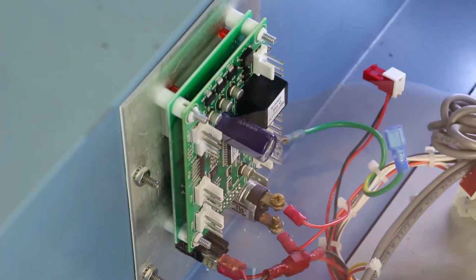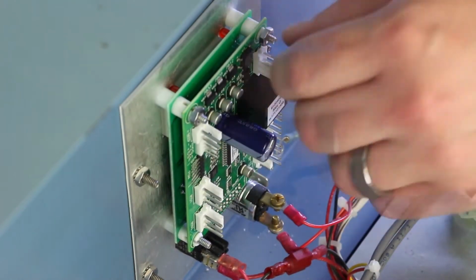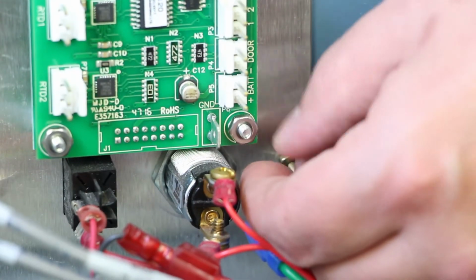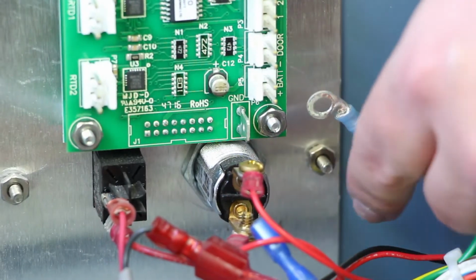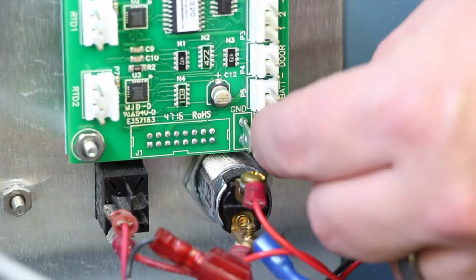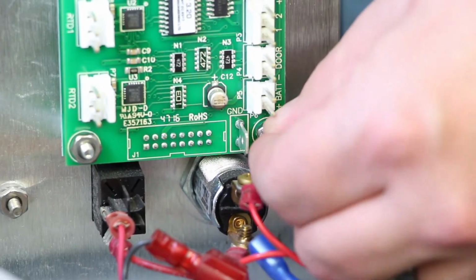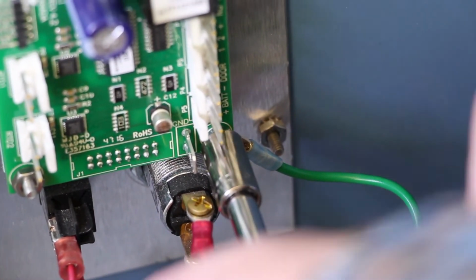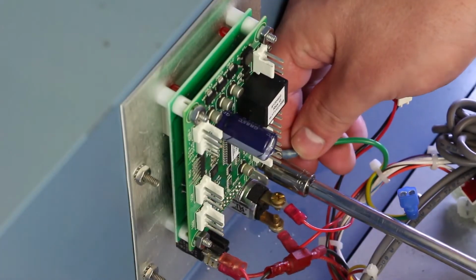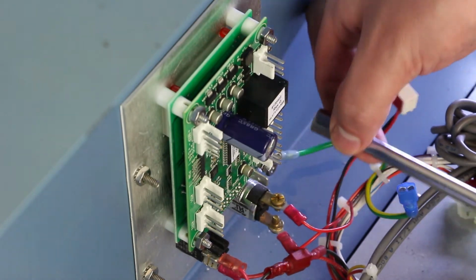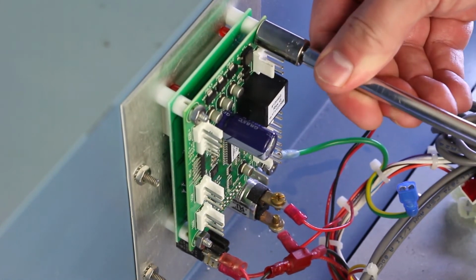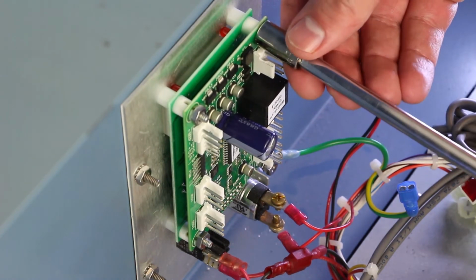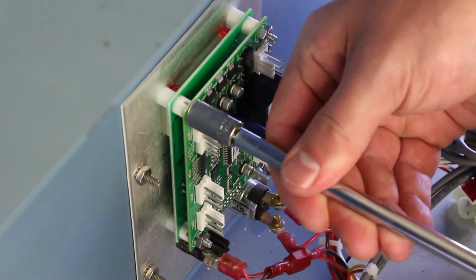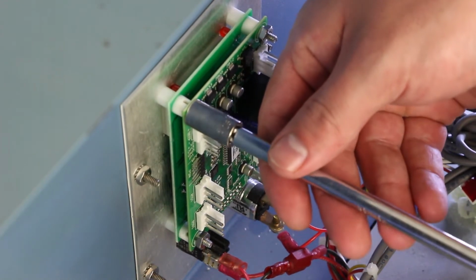Ensure the plastic spacers are in place between the circuit board and the back of the membrane. Use the 5/16 socket to tighten the nuts back in place. Take care not to over-tighten them, which can push the circuit board too far into the back of the membrane, activating the buttons even when they are not being pressed. If they're not tightened enough, the buttons can be difficult to press.